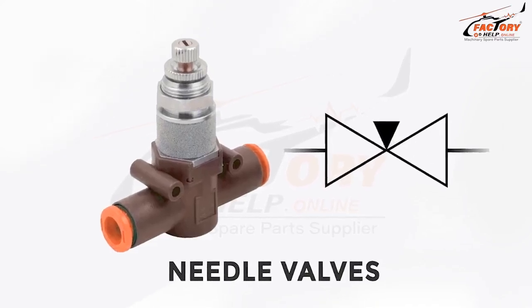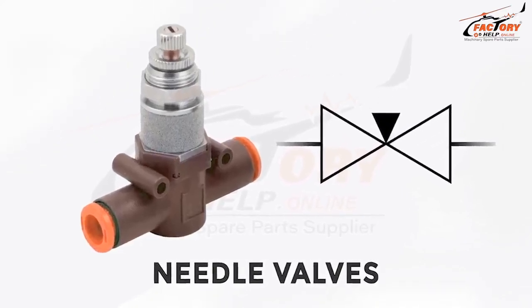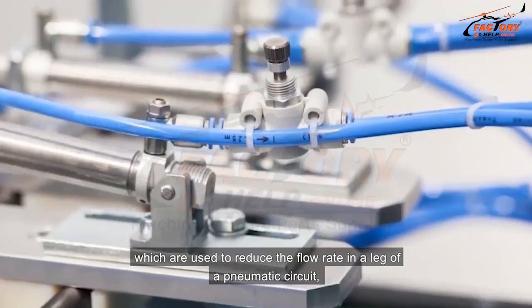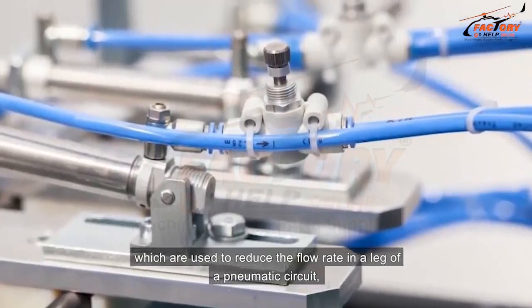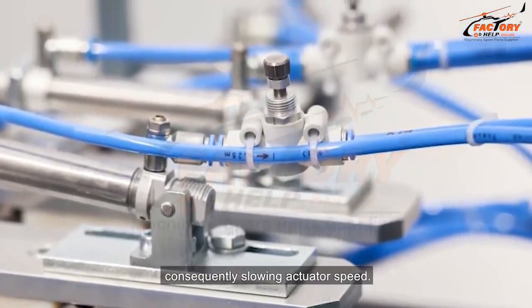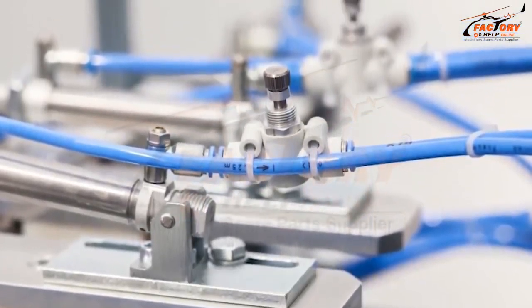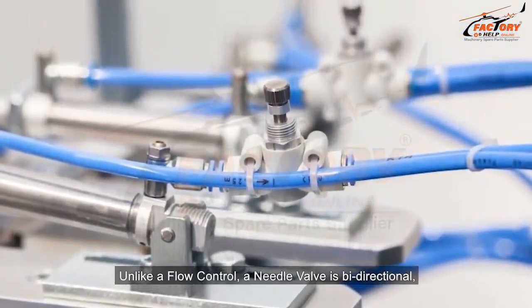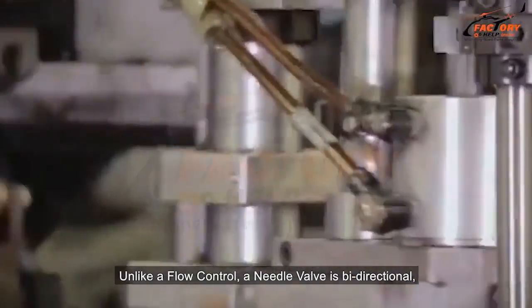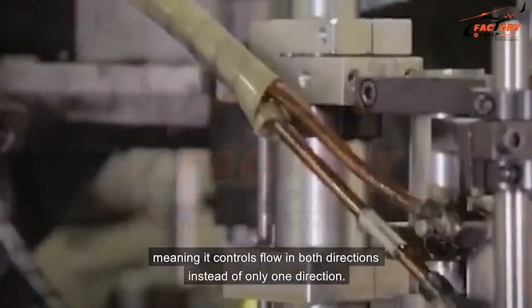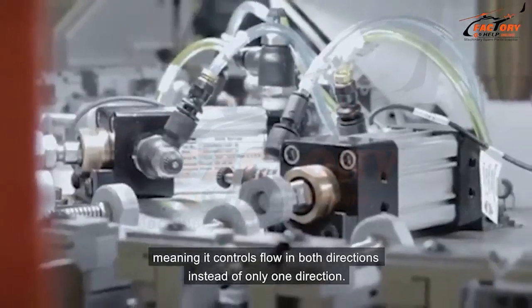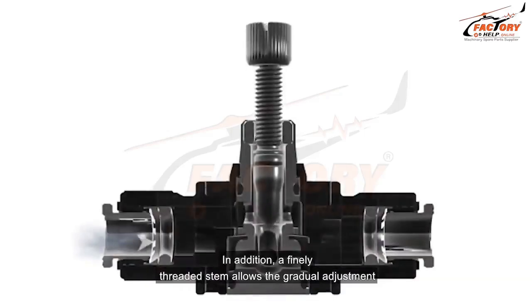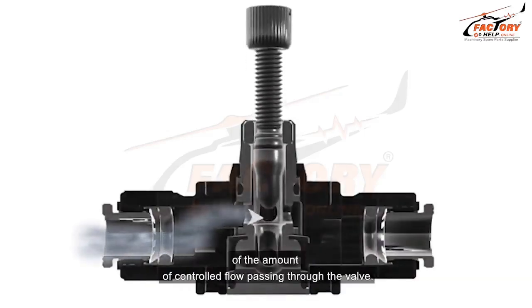Needle Valves Factory Help presents the pneumatic needle valves, which are used to reduce the flow rate in a leg of a pneumatic circuit, consequently slowing actuator speed. Unlike a flow control, a needle valve is bidirectional, meaning it controls flow in both directions instead of only one direction. In addition, a finely threaded stem allows the gradual adjustment of the amount of controlled flow passing through the valve.